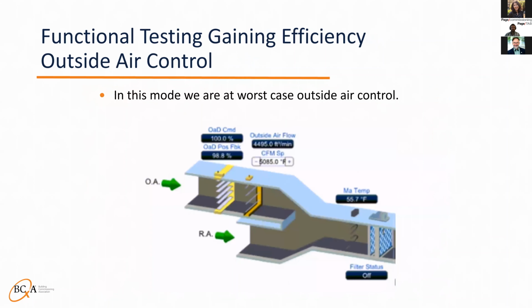So before getting out of heating, let's look at the associated AHU's outside airflow versus its set point. We can also look at its damper position. When all terminal units are driven to heat, the AHU will operate at its lowest speed, which, again, is mainly for warmer climates. And when it operates at its lowest speed, it is the hardest to get its design outside air. This is the best time to check this value.